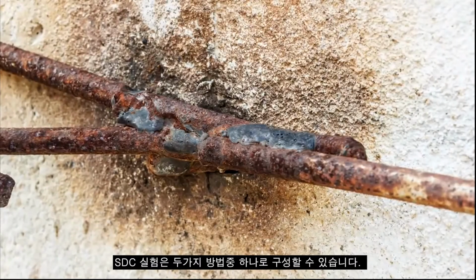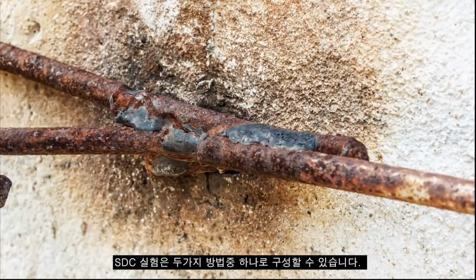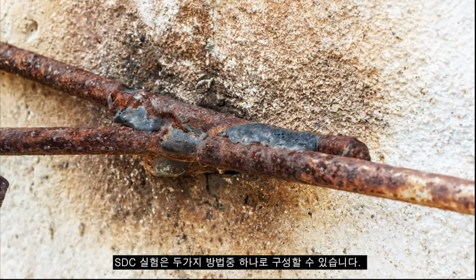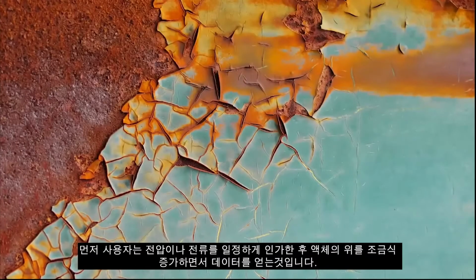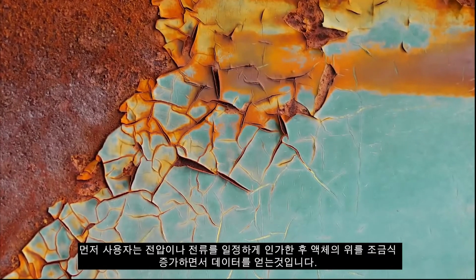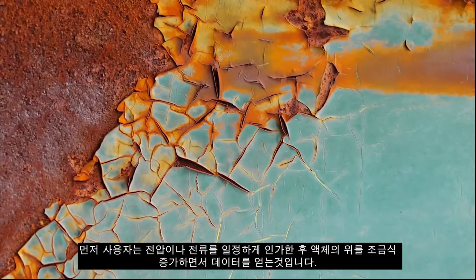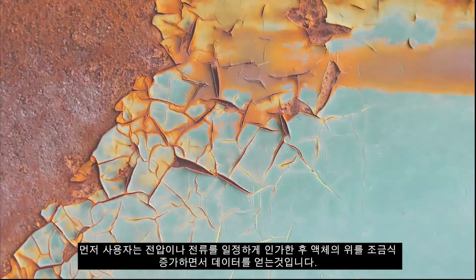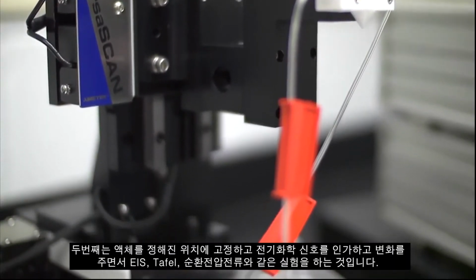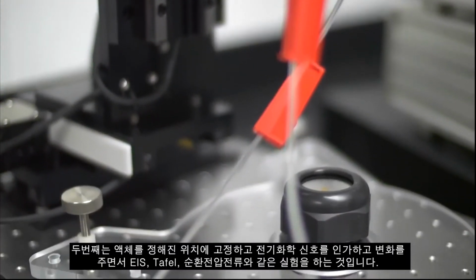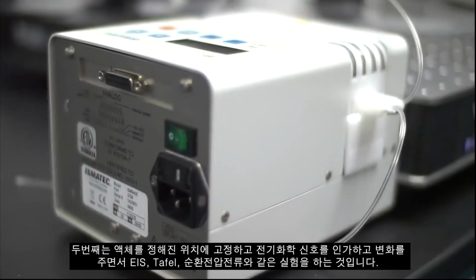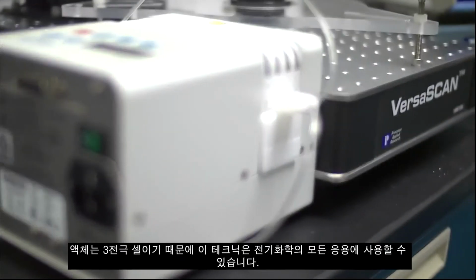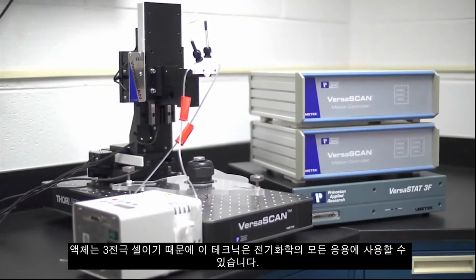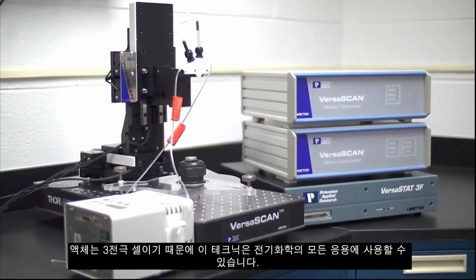First, the user can apply a constant bias, such as potential or current, and increment the position of the droplet, creating a data map. Second, the user can apply a static or dynamic electrochemical signal to perform experiments such as EIS, Tafel or cyclic voltammetry, as the droplet is held in a fixed location. Because the droplet is a self-contained 3-electrode chemical cell, the technique applies to all applications of electrochemistry.